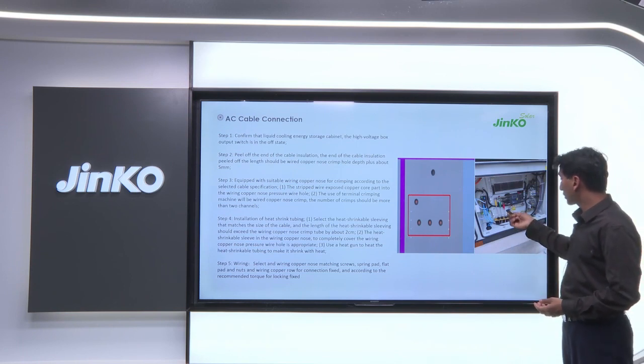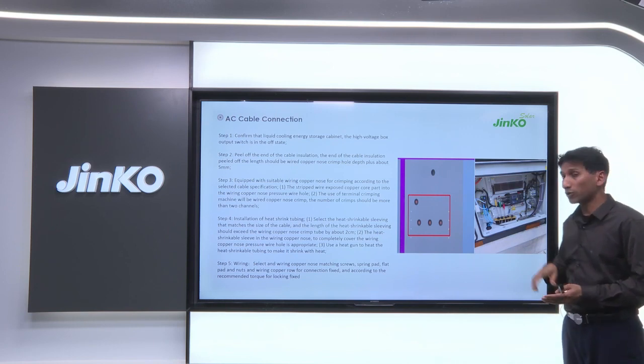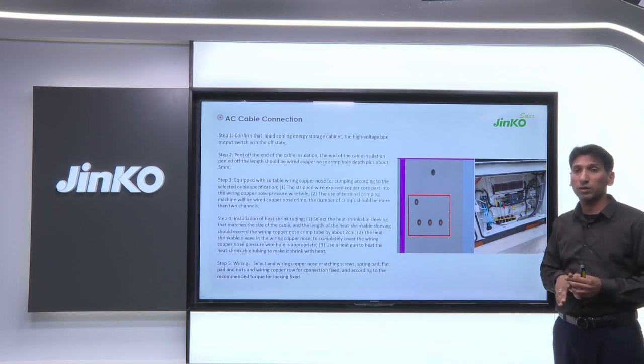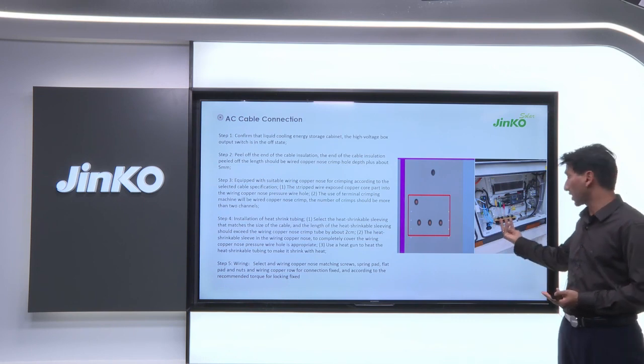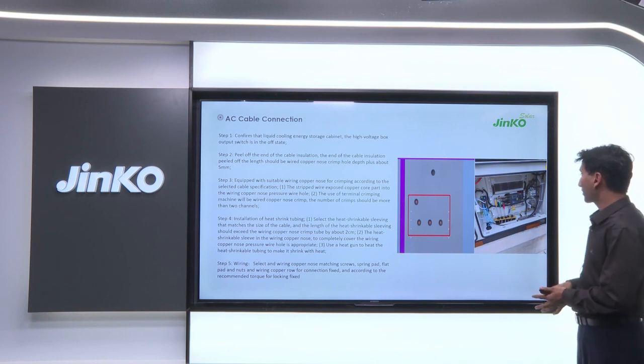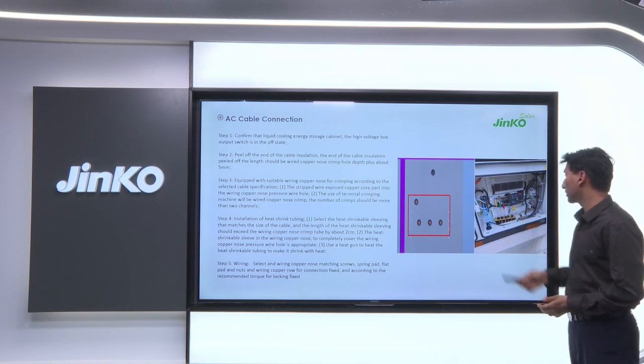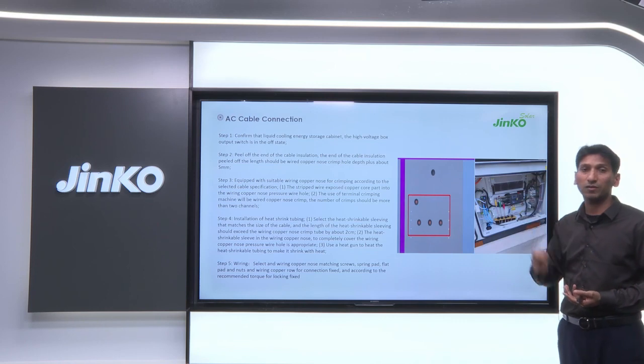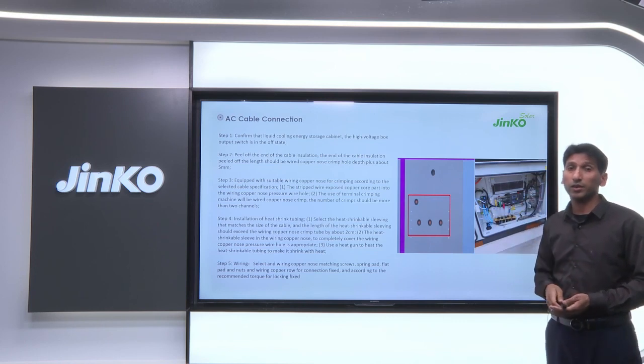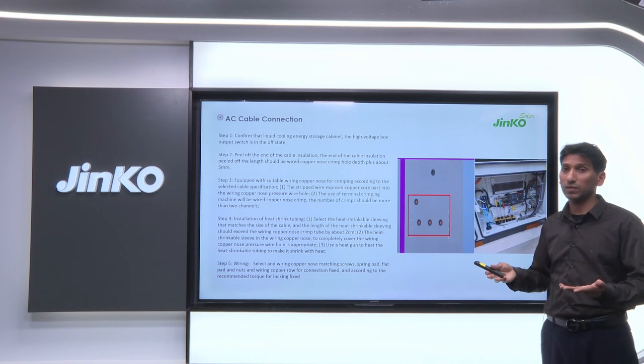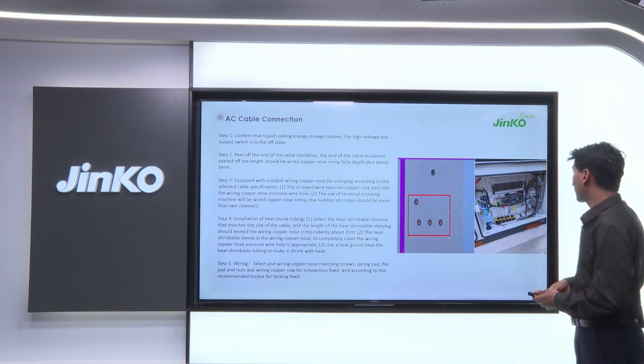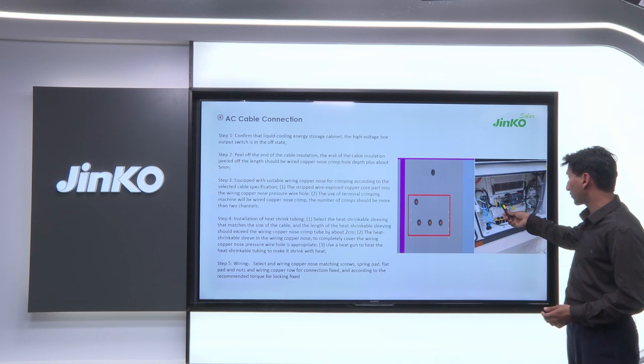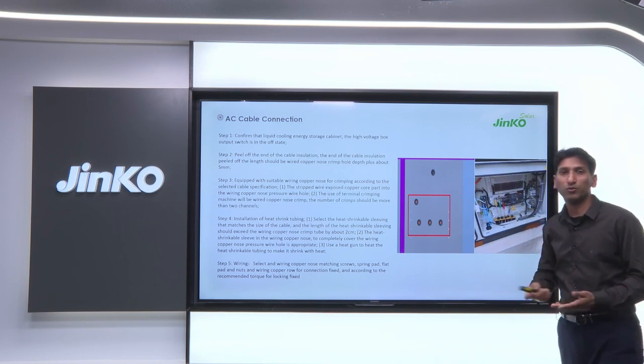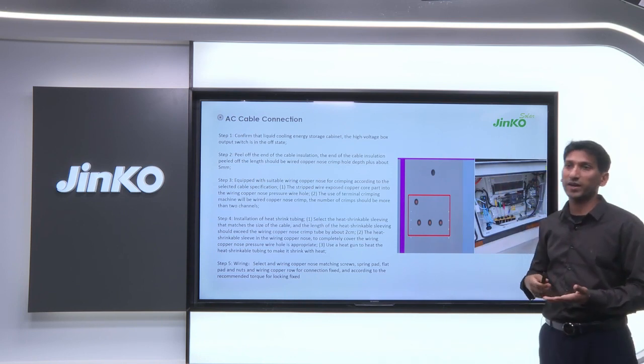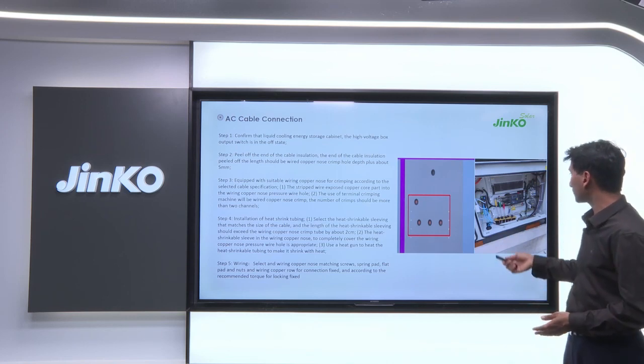You can use them, but you have to be very careful about the phase sequence of the cable, because there are so many units. If you're connecting 8 or 9 units, the phase sequence should be the same in all of them, and the best practice is to mark each phase with some color, so you do not make a mistake. If there's a phase sequence mistake when you connect with the grid, it can cause a phase sequence fault on the grid, and everything can trip. So you take the AC cables from here, and then you can connect to your system wherever you want to connect, whether that is a combiner box or directly connected to the grid, or whatever other side it is.